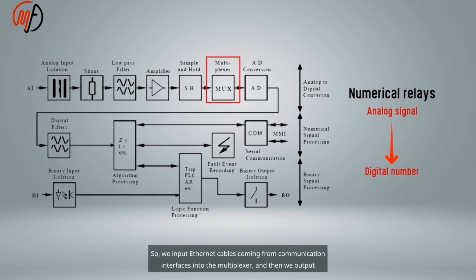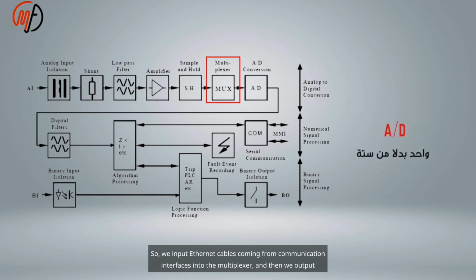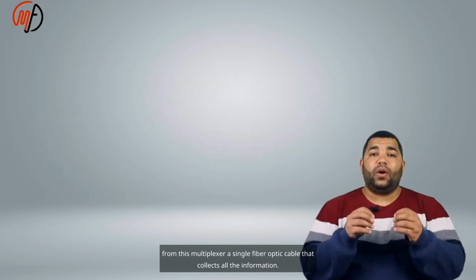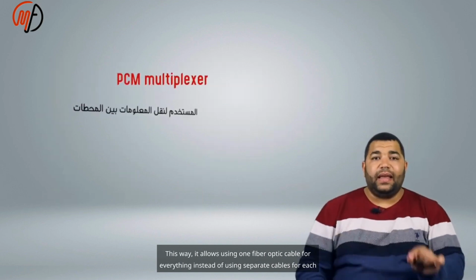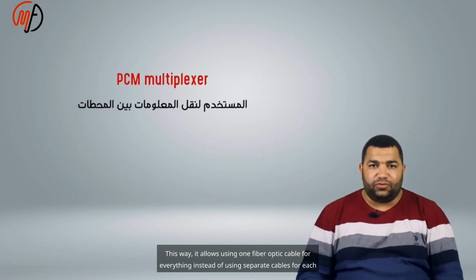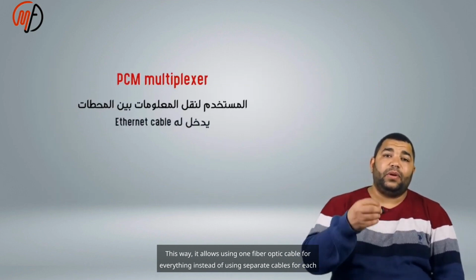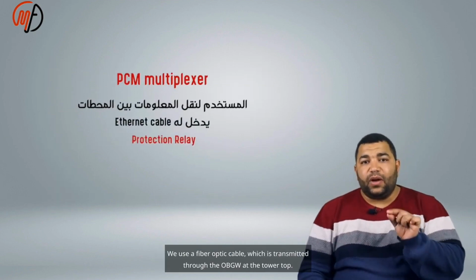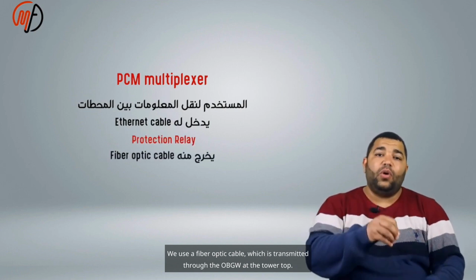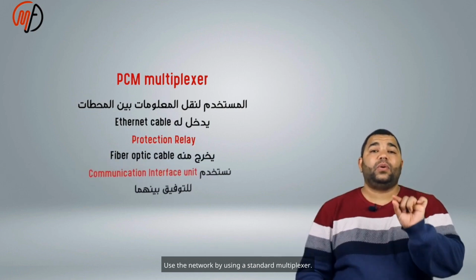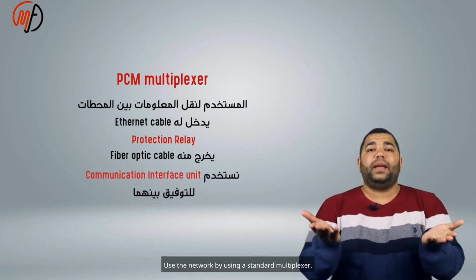So, we input Ethernet cables coming from communication interfaces into the multiplexer, and then we output from this multiplexer a single fiber optic cable that collects all the information. This way, it allows using one fiber optic cable for everything instead of using separate cables for each signal. We use a fiber optic cable, which is transmitted through the OPGW at the tower top. Use the network by using a standard multiplexer.